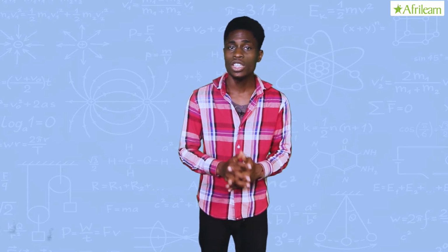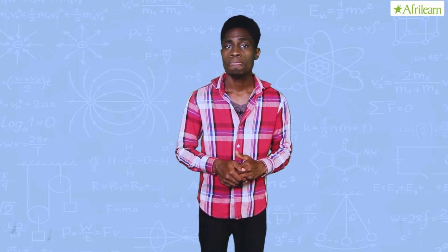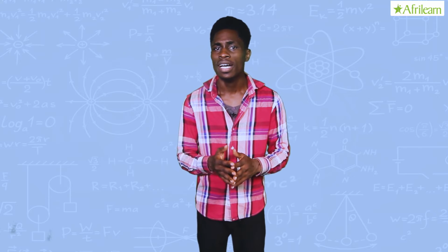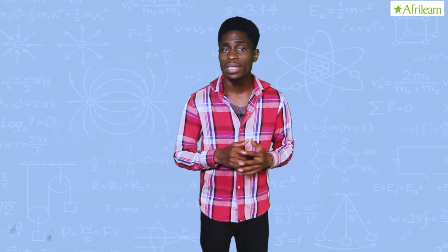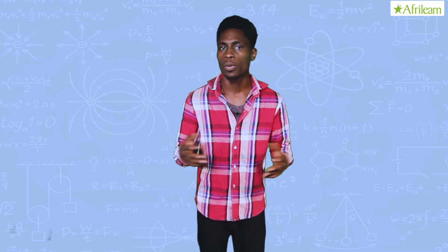The specific gravity of the electrolyte is of importance to the correct functioning of the cell. When the cell is fully charged, the specific gravity of the electrolyte is about 1.21, but when the cell is discharged to 1.8 volts, specific gravity is about 1.18.